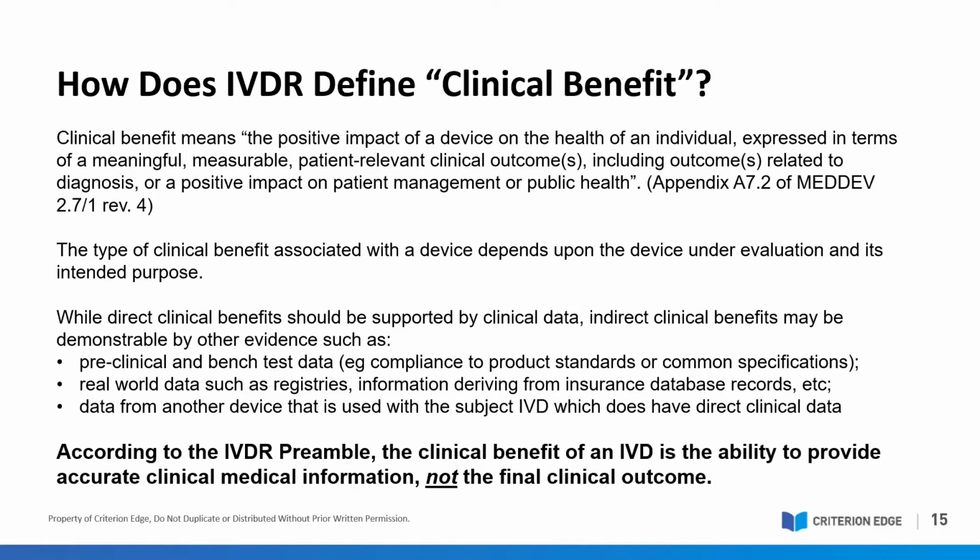But I'd like to just point out a key distinction between clinical benefit in terms of how MDR and IVDR define it. Unlike medical devices, which have a direct impact on patient outcomes, the clinical benefit of an IVD is the ability to provide accurate clinical medical information, not the final clinical outcome for the patient.